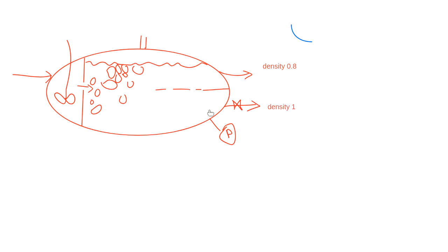If you measure the pressure there, and you know the height between this point and the offtake over there, you know the height up to the top there, and you're measuring, let's say, the dP across that, from that point to that point. If you control this flow rate, if you take off more water, then this interface will actually move downwards, and the average density will get less where you're measuring this pressure. So you'll measure a lower pressure. And I'm talking about a rho g h pressure that occurs across that point. And so you simply have to control this pressure such that the density equals about 0.9, somewhere between these two densities. That will ensure that the interface stays between the two offtakes.